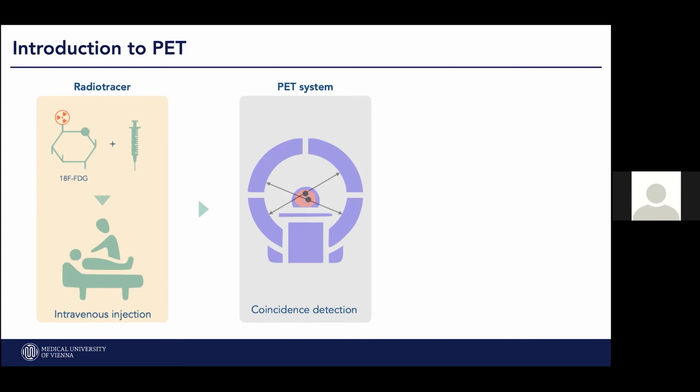Once they are injected into the patient, the radiation is emitted from the redistributed tracer molecule, and it's being detected typically by rings of scintillation detectors arranged around the patient. Normally, and depending on your budget, the axial field of view is an order of magnitude longer than in CT, but certainly not yet covering the entire body, as you will see in just a short while.